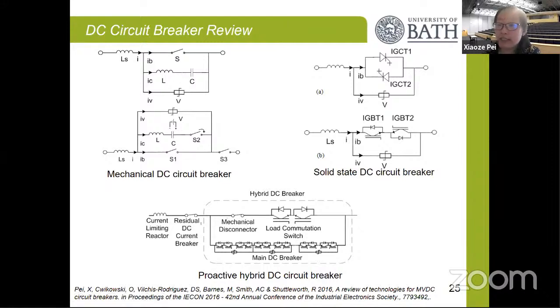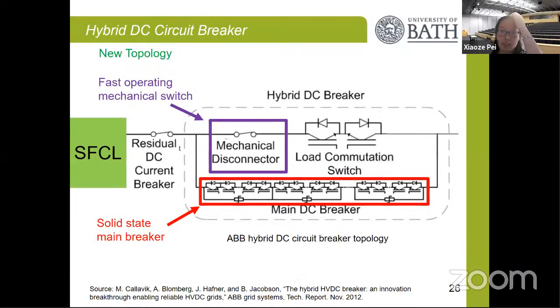Because the solid state DC circuit breaker only takes the current for a very short period of time, just a few milliseconds, 1 to 3 milliseconds, the losses don't matter that much. So this is a combination of low losses during normal operation and very fast interruption during the fault condition. The research in our group is around the hybrid DC circuit breaker.